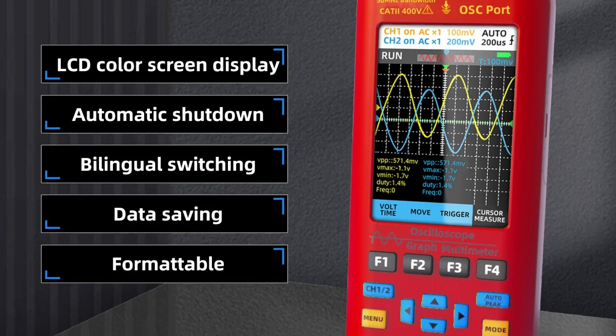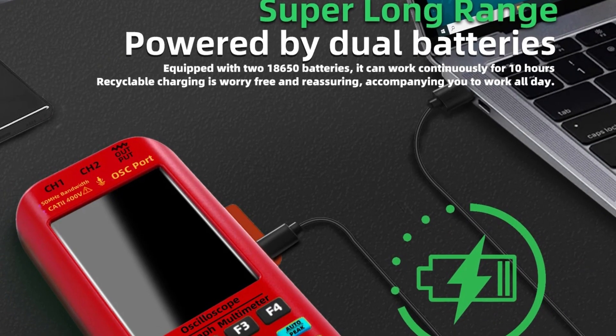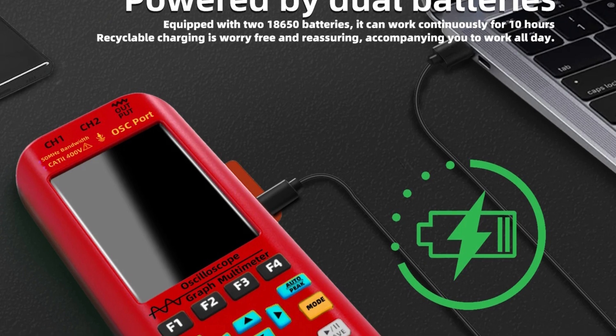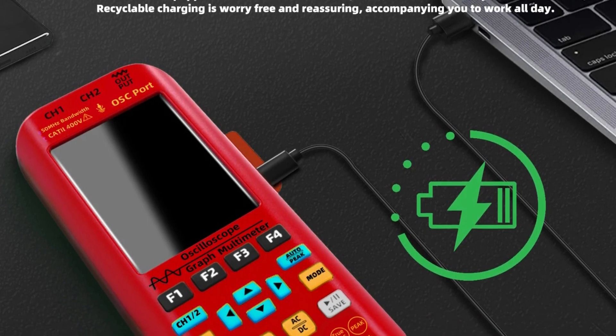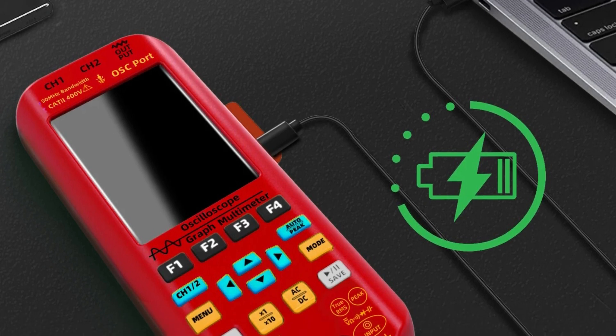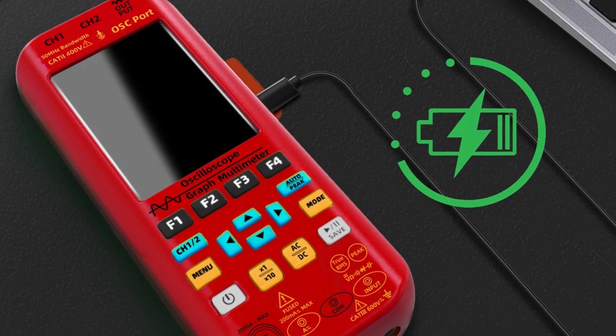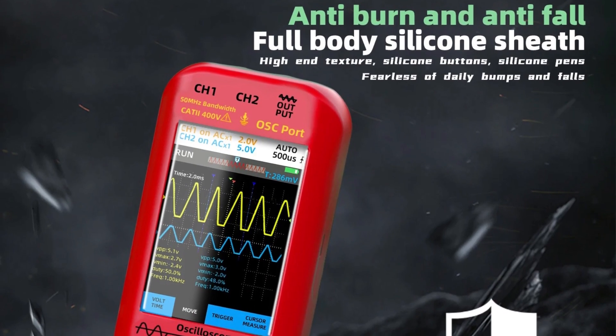One of the key features of the B-Side is its built-in high-voltage protection module, which supports peak voltage measurements up to 400 volts, ensuring safe and reliable operation even in demanding conditions. The oscilloscope also comes with a 3.98-inch full-view high-definition TFT display offering a resolution of 480 × 320 pixels, providing clear and sharp visuals for on-the-go analysis.